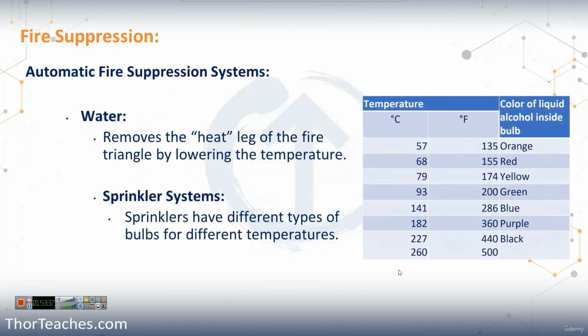Then we talked about how in all of our building we would have sprinklers. Each sprinkler head has a little glass bulb that once it reaches a certain temperature, that bulb breaks, water comes out. Now in the rest of the building, perfectly fine, not a problem. But in the data center, that needs to be the very, very last resort. Because when you put water on your hardware, it's completely dead. That is just in hardware, millions and millions of dollars. We use sprinkler systems in the data center when the data center is lost and we need to preserve the building. And that's of course only after the main fire suppression, whatever gases we have, failed.